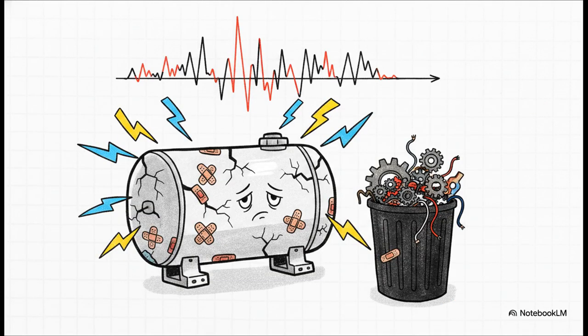Each erratic start and stop places massive stress on the unit's electrical and mechanical parts. It spikes your energy bill every single time that motor kicks on. It guarantees inconsistent comfort across the building, and it drastically reduces your equipment's life expectancy. The fix here isn't just replacing burnt-out parts. You have to play detective to find the underlying cause. That could be oversized equipment, poorly placed thermostats, or even restricted airflow causing internal safety devices to constantly trip.